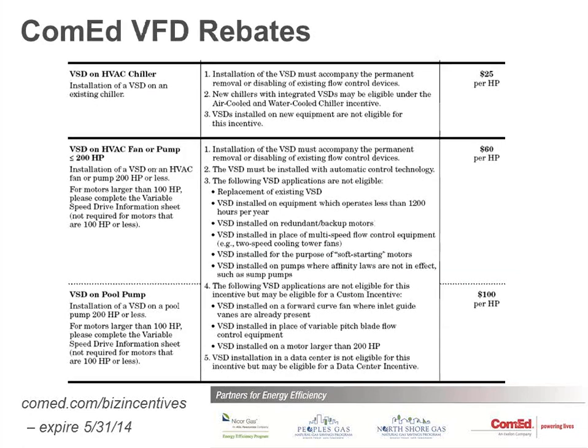VFD rebates are by far the most popular HVAC-related rebate on the ComEd program. If you put a VFD on a fan or pump, it is $60 per horsepower. Basically, for applications where you're replacing inlet guide vanes is where you're going to be using this. You can also use this on a brand new rooftop if you're doing staged air volume control. That's a newer concept that's become more popular in the past couple years, where you're staging the VFD speeds depending on how many stages of heating and cooling are running or ventilation mode. This does apply to that. So you can get $60 per horsepower for putting in a new rooftop that has built-in SAV control.